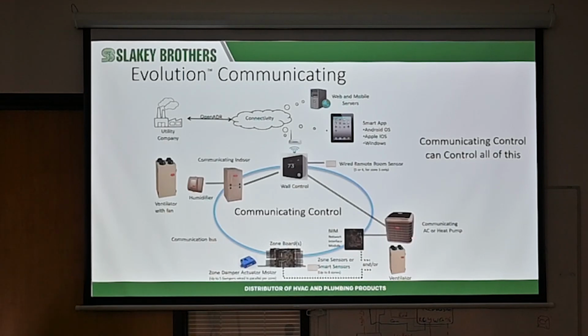Extra features are on there, like a network interface module. Again, you can install this if you're doing Evolution; it means you at least have an Evolution furnace or an Evolution air handler. For whatever reason, if you have a scenario where they're going to wait and use an older condenser and then install another condenser in a month or two, you can work an Evolution control, Evolution furnace, or Evolution fan coil with a non-Evolution heat pump or non-Evolution AC unit. If it's a heat pump, it's got to be a fan coil though. If you're doing a non-communicating outdoor unit and you're trying to do dual fuel, it won't be able to do it unless the outdoor unit is also an Evolution unit. Anyway, communicating-wise, you can see it doesn't communicate to the humidifier. It doesn't communicate to the ventilator.